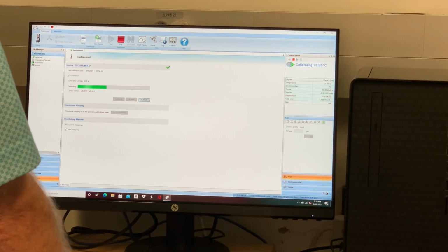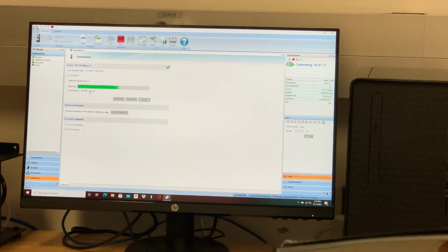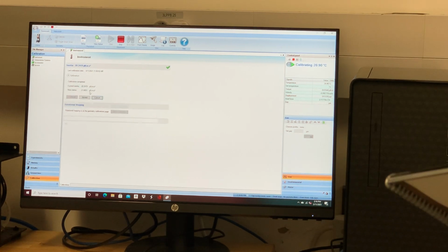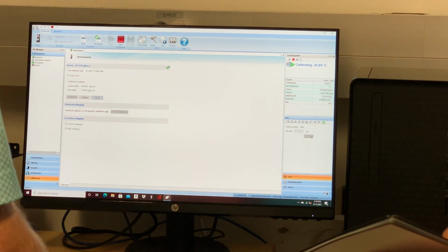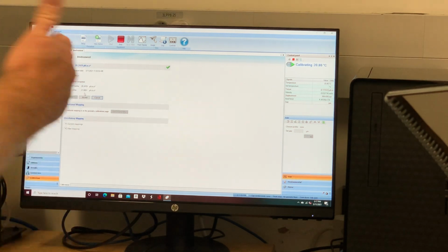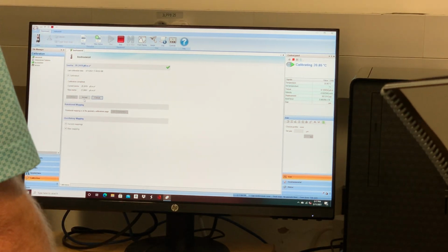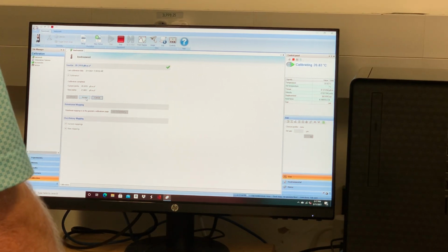It gives you the last calibration date, time, and the value you had. And if you do this calibration, it should be very close to the last number. It's going to be a little different, but the last one was 20.2. This one's 21. So 21's around normal. What's the acceptable deviation? If it goes over 22, there may be an issue with the bearing. And you just hit accept.